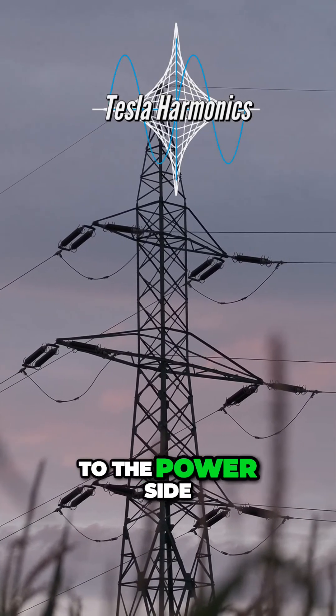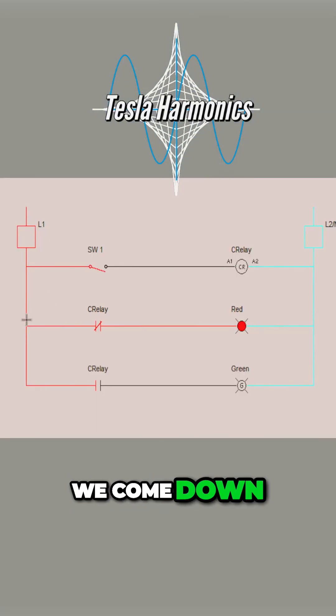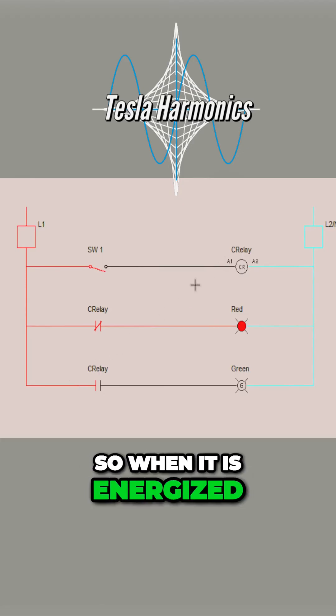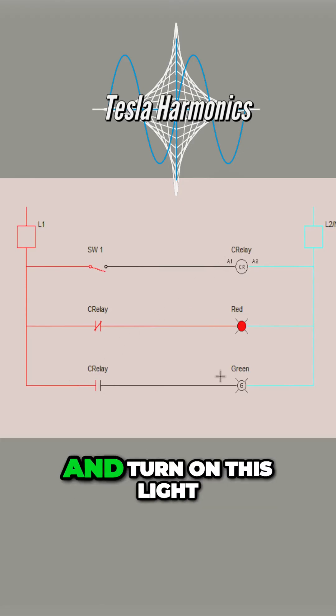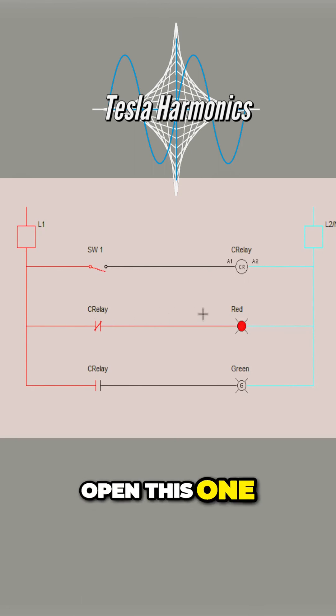We come back over here to the power side. We come down, we have also taken and put power on one side of a normally open contact that is on that control relay. So when it is energized, it's going to close this one and turn on this light, open this one and turn off that light.